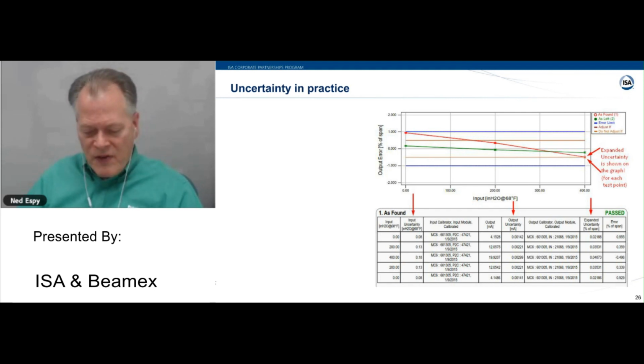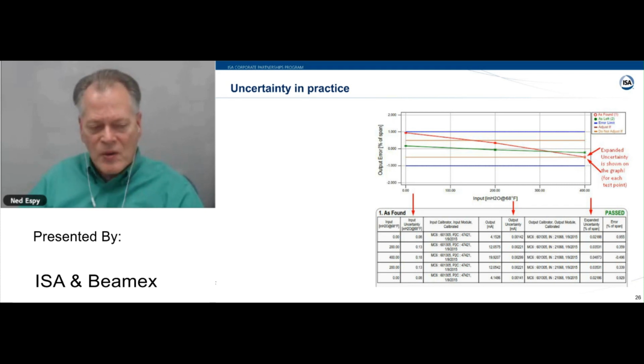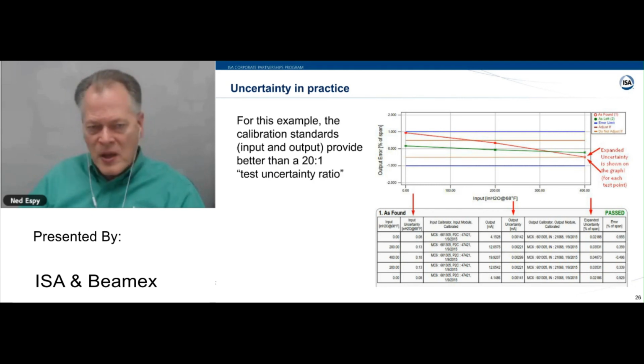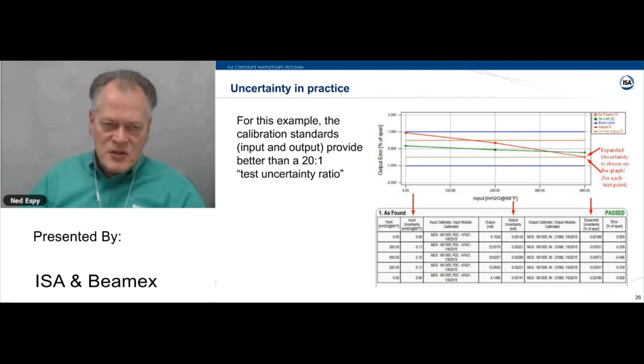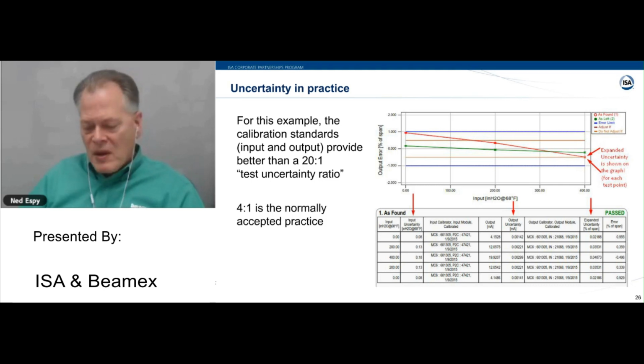And remember, we have a window of what the true measurement is, just a numerical estimate with a 95% confidence level. But in this example, it's a 20-to-1 ratio. The standards are 20 times more accurate than what you're trying to achieve in the process. This is a test uncertainty ratio, or you'll see the term TUR. You should note that 4-to-1 is sort of the normal practice. It's kind of an old military practice that you want your standards to be 4 times more accurate than the process instrument that you're trying to test.